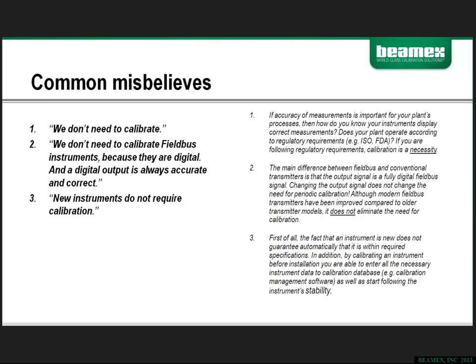This, in turn, will set a baseline for stability analysis and gets the required instrument information into your calibration maintenance database. So calibration doesn't only serve in this respect to ensure that it's good, but it's also a way of getting all the particular information for that particular asset, be it the manufacturer, model number, serial number, the specific program information, if it is, for example, a field bus device, so that it's already in your system and will be tracked as such from that day forward.